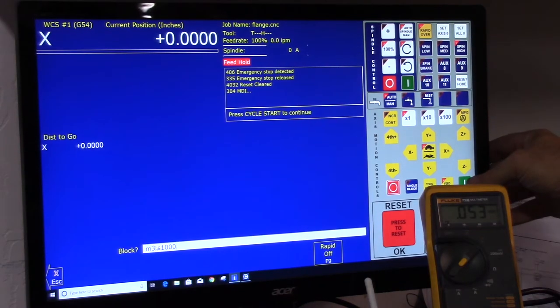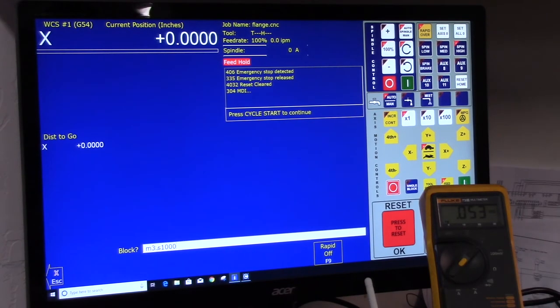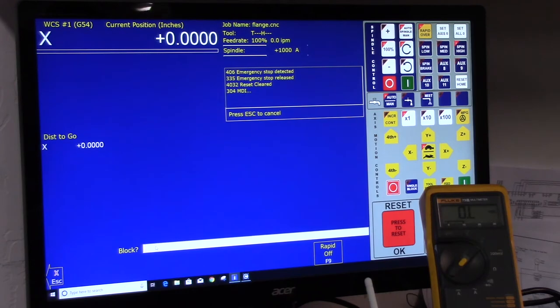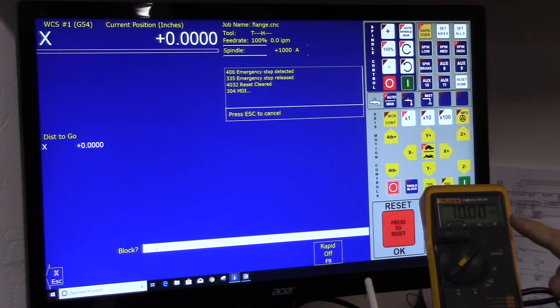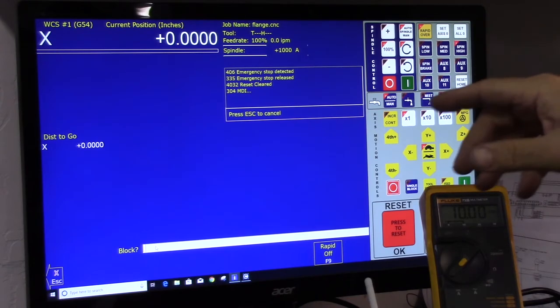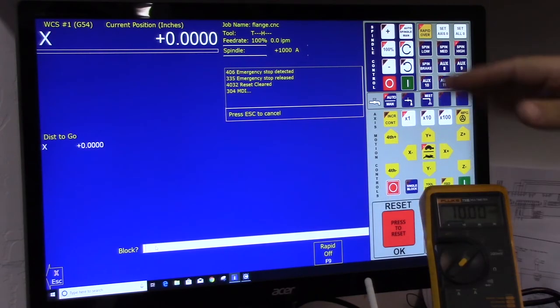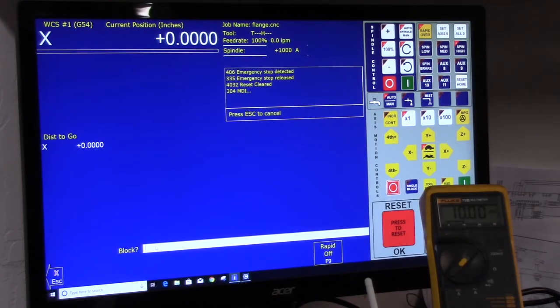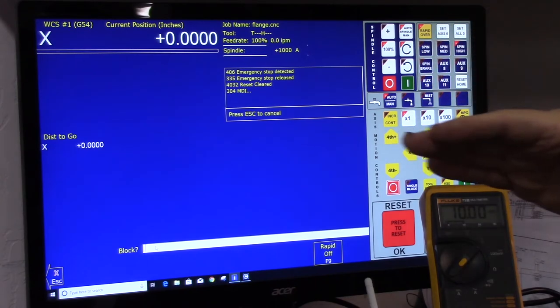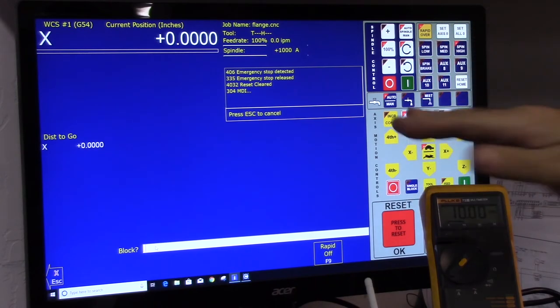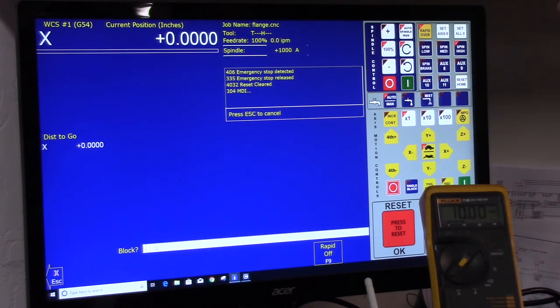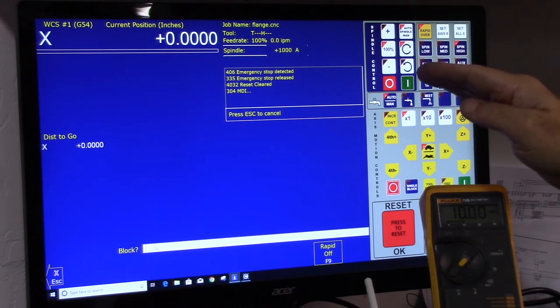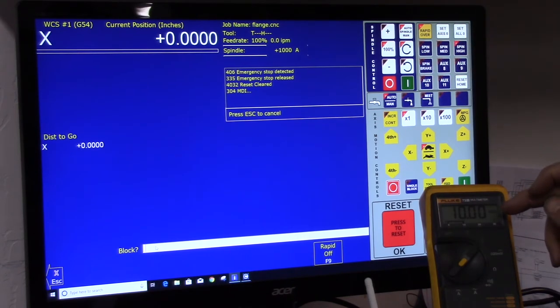You can hit the green button over here on virtual control panel, or you can do Alt-S on the keyboard. I'm going to do Alt-S on the keyboard. Now you see right here, the voltage is 10 volts because we called the max speed. The voltage is linear with the RPM. So I chose 1000 so it's easier for us to see when we're calling the highest speed of 1000, we should get a full 10 volt analog output.